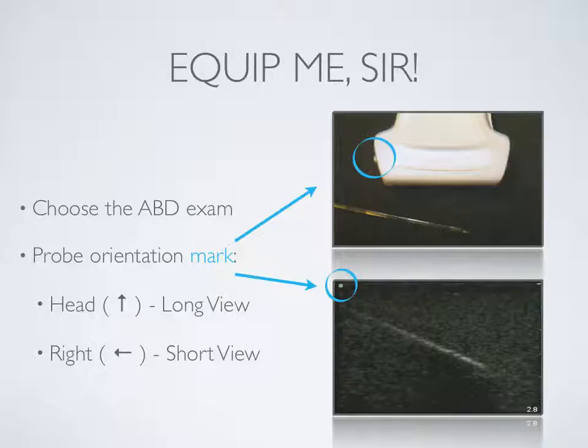Each probe will have a mark that you can typically feel when holding the probe. I have it circled here on a linear probe, and this allows you to orient the mark with a dot or a logo on the screen. Here we have a green dot on a corresponding ultrasound screen. Oftentimes you'll see a letter or a logo. It's usually a brand logo or the first letter of the machine name or something that indicates what alignment the probe is going to be with the screen. If it's in a location that you don't like, there's usually a toggle button somewhere very easy to find on the machine that you'll keep pushing until it circles around to the location you want.